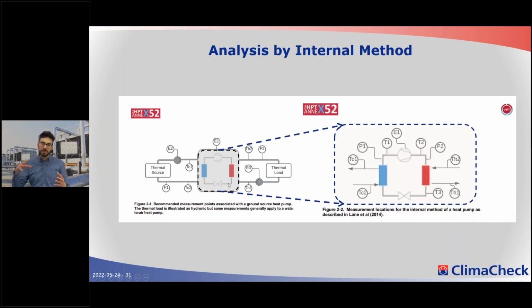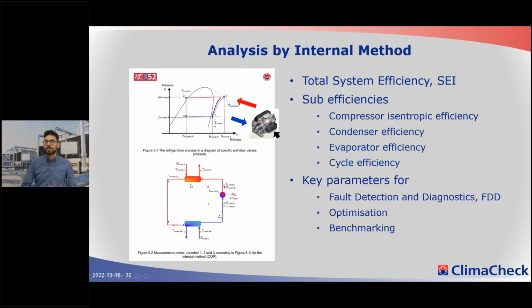What we like to do is dig into that black box, open it, look at the sensors, how they're working, how the system is working, how each component is performing, and how we can improve it. Now, this is called the internal method, and is basically based on thermodynamics. What we are aiming to get from this internal method is the analysis of the whole system, the system efficiency index, and the efficiency of each component, the compressor, condenser, evaporator, the cycle. What we can also get from it is fault detection, to predict if something is going to happen and be able to fix it before any breakdown or failure. We can also have optimization and benchmarking compared to other systems.